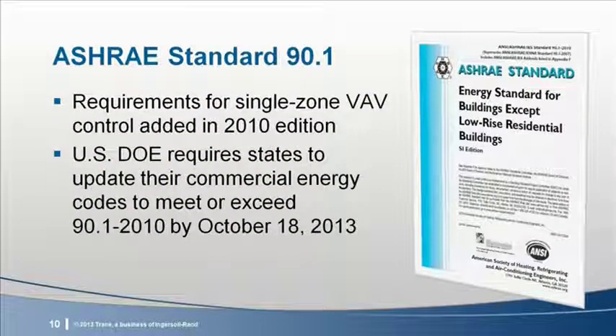One of the reasons for producing a program on this topic is because requirements for SingleZone VAV control were added in the 2010 edition of ASHRAE Standard 90.1, the energy standard for buildings. SingleZone VAV requirements are also included by reference in ASHRAE Standard 189.1 2011, the standard for green buildings. And this is especially significant because the U.S. Department of Energy has mandated that states must update their commercial building code to meet or exceed Standard 90.1 2010 by October 18, 2013. So if not already, these new requirements will soon be impacting many state codes.